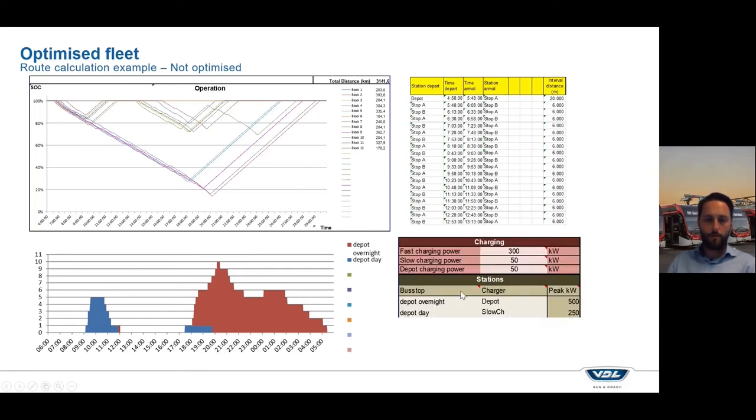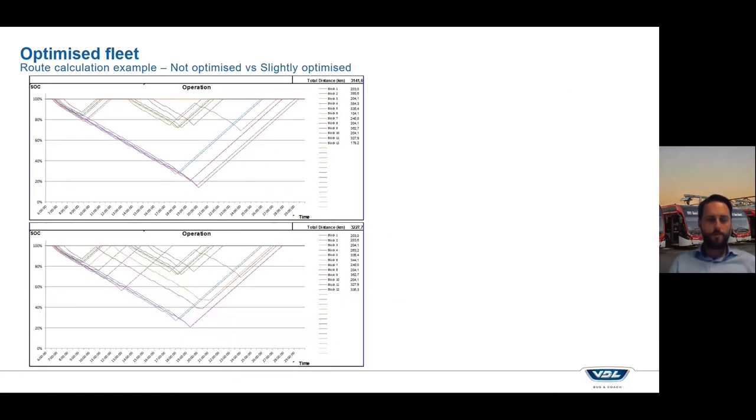In total, you need 500 kilowatts as a peak grid connection at one point, which is very simply just the 10 chargers that we have active at the same time times 50 kilowatts of depot charging power results in 500.